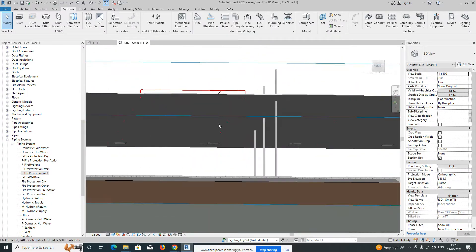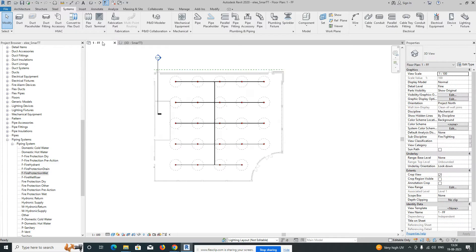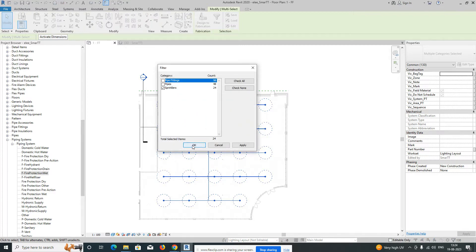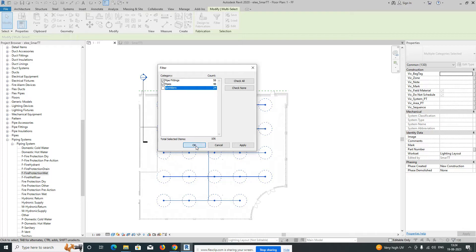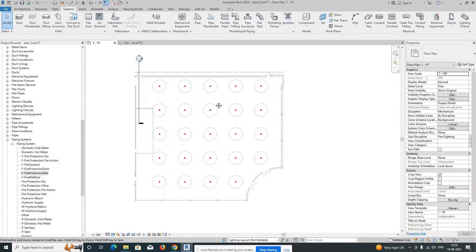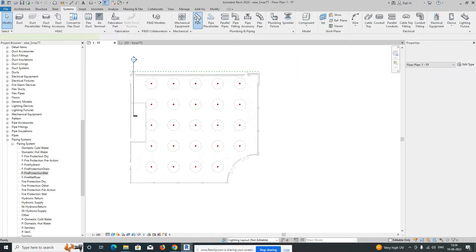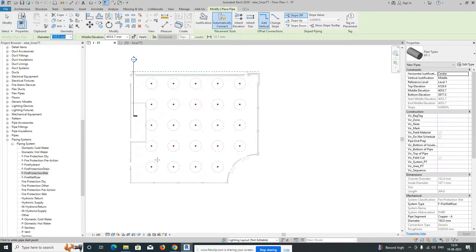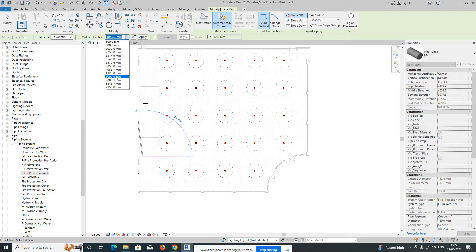Now I'll show you another way to connect the sprinklers. All sprinklers are connected to the main branch in the auto method. For the manual method, I'm deleting all the pipes — using Filter, unchecking sprinklers, then deleting all pipes. Now I'll manually create the main branch pipes. I already have a firefighting pipe type set up. I'm using 150mm diameter and starting the main pipe at a height of around 5000mm.